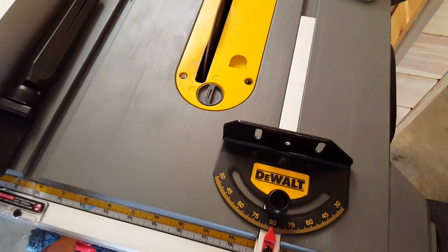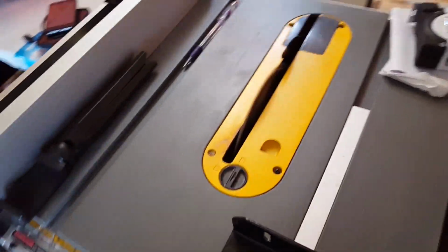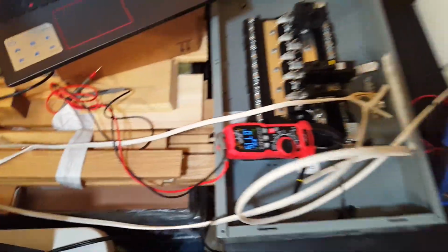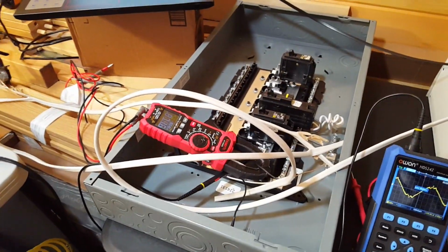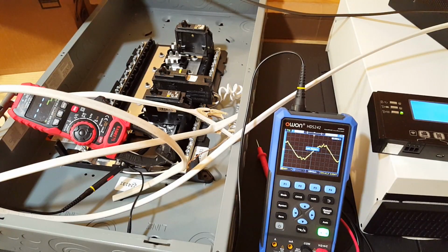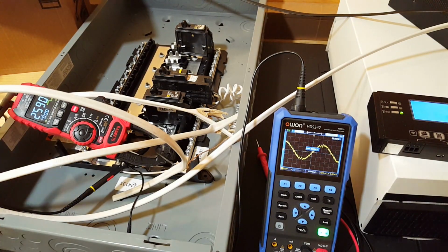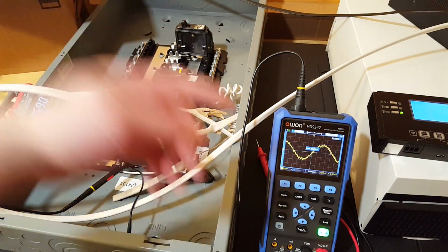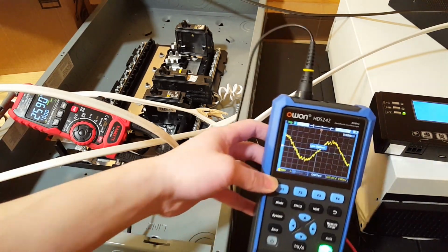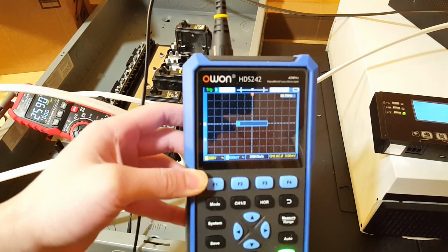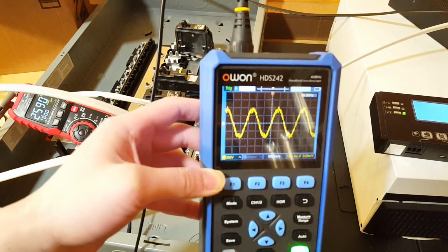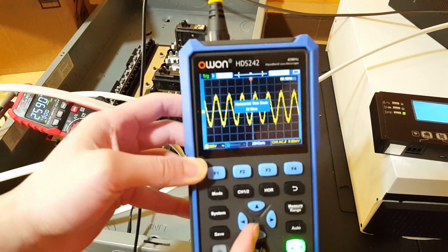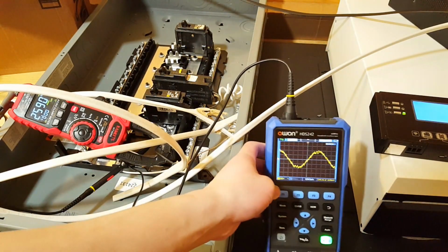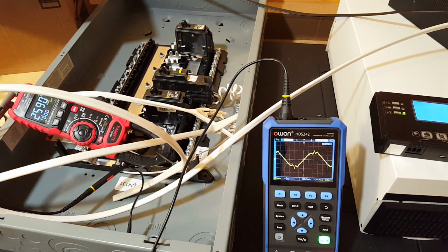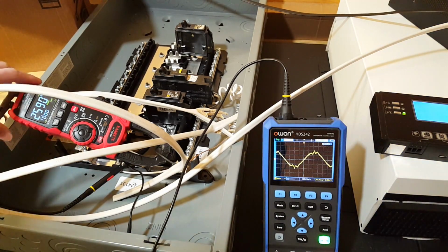Let's reset the clamp meter and try that one more time. Surge 71.5. Going to battery mode, you can watch the waveform and the surge amp. Will it start it? 65 amps. Wow. This is the waveform on battery mode. Have a look at that. Okay, so it was able to do it. We saw 65.2 amps AC inrush.